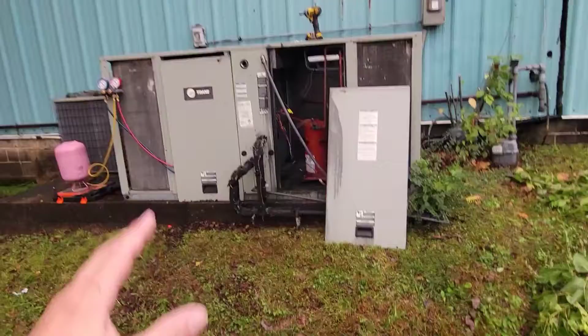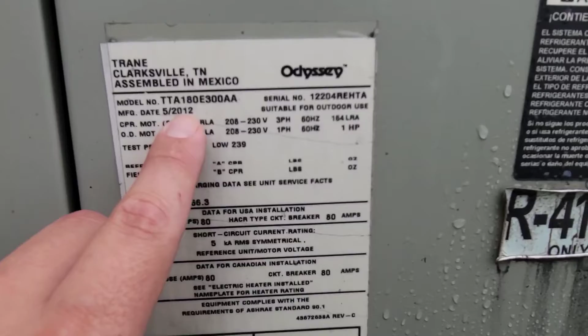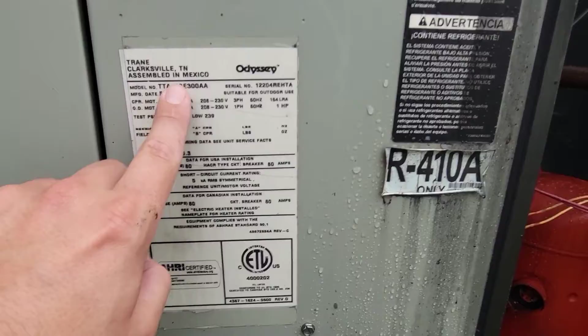This right here is a 15-ton condenser. How do I know that? I check the side here, it says TTA 180. If you divide 180 by 12, since 12 is 1 ton, you get 15 tons. You see how it's 410A?